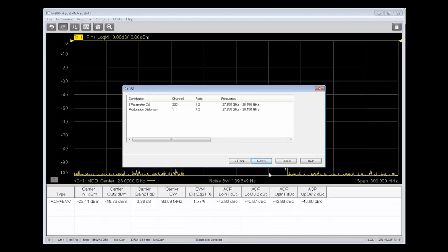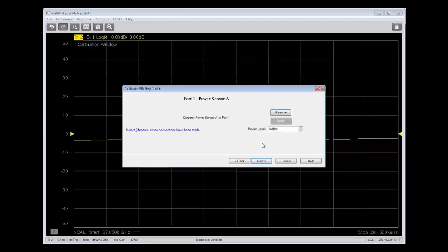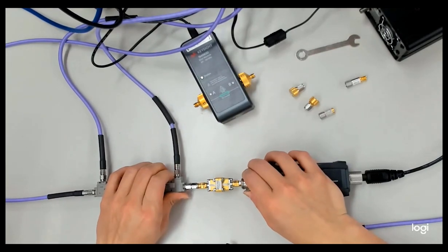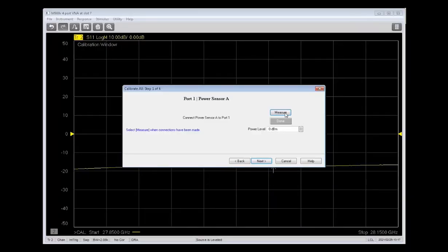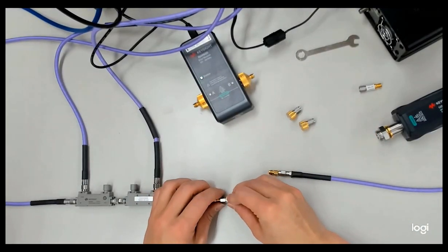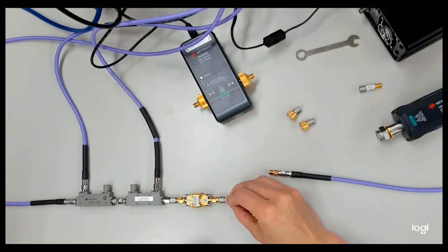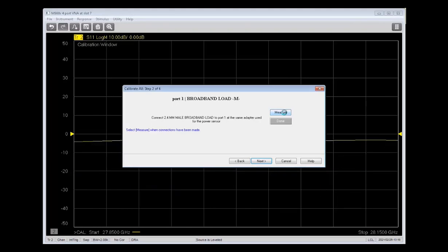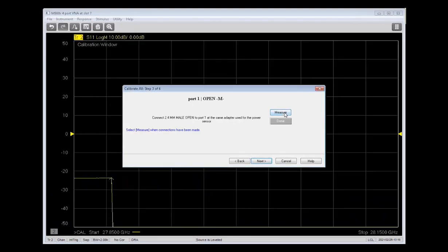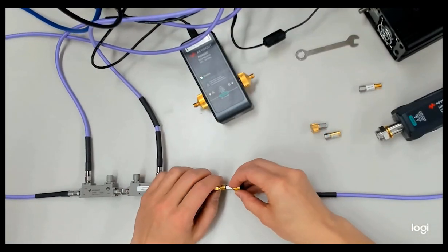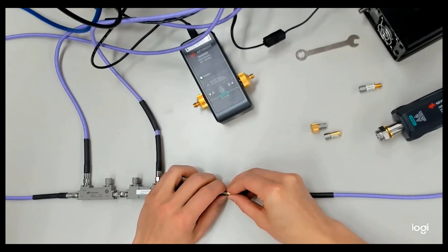And then we'll verify everything looks good and hit Next. And then now it's time to connect the power sensor to port 1. We're going to use that adapter that we specified earlier, and then just connect it right on to the measurement port. And after you connect the power sensor, click Measure, and the instrument will perform a power calibration. I've sped up these calibration clips for the purpose of this demo. And then once the power calibration finishes, it'll prompt you to connect a broadband load. You go back into the instrument and click Measure to perform the calibration on the load. And once that finishes, the instrument will prompt you to connect an open.